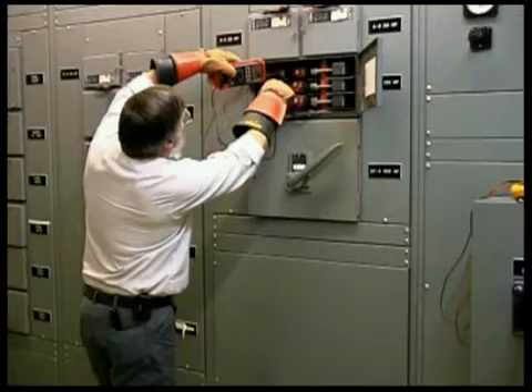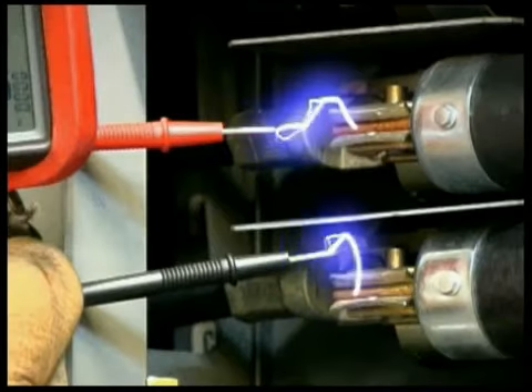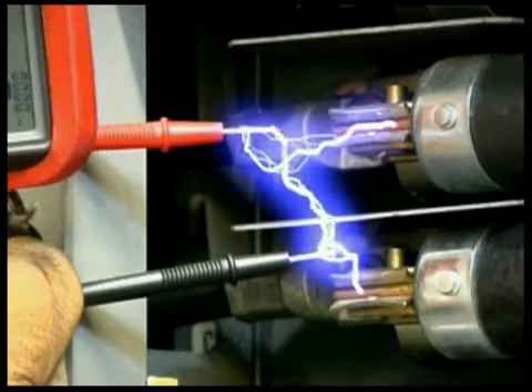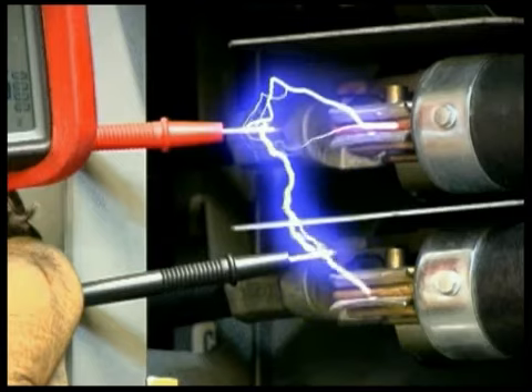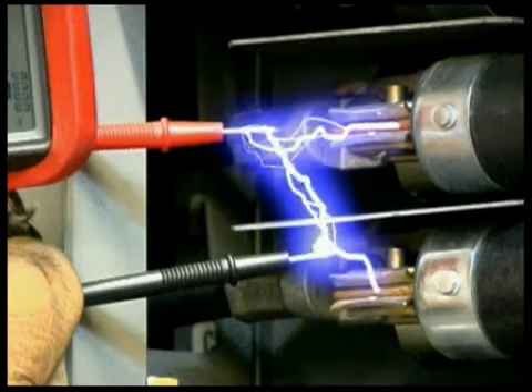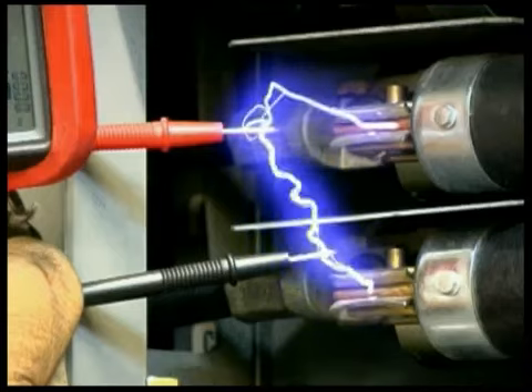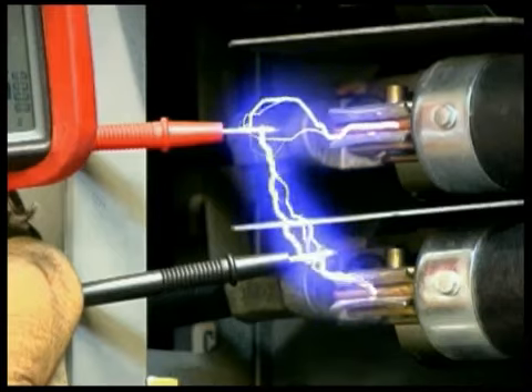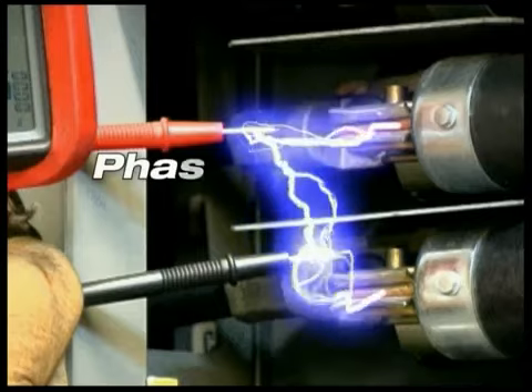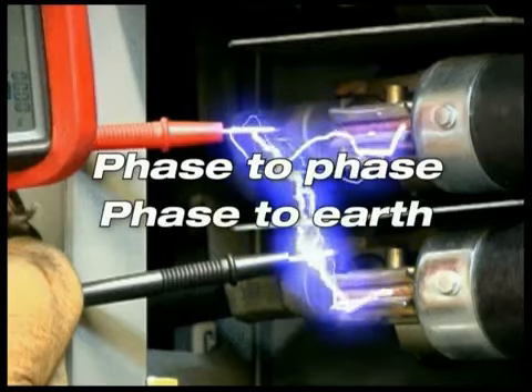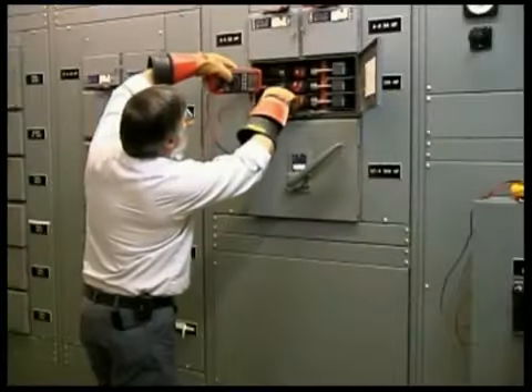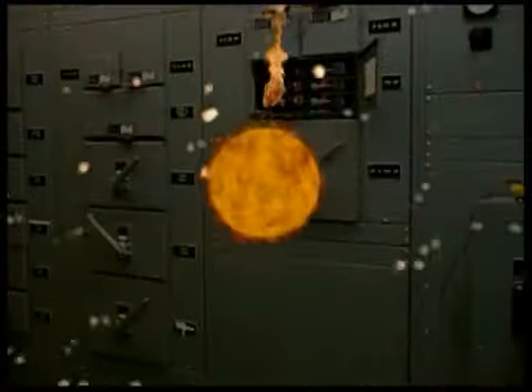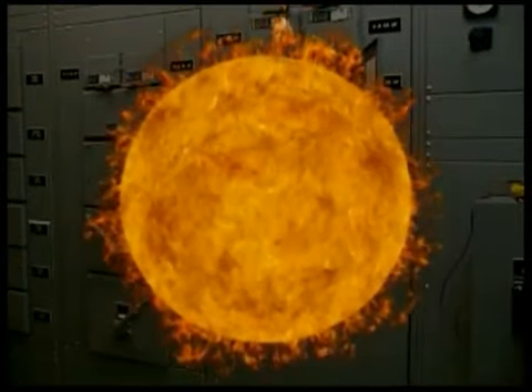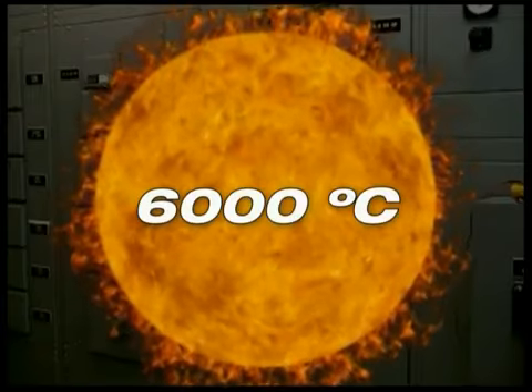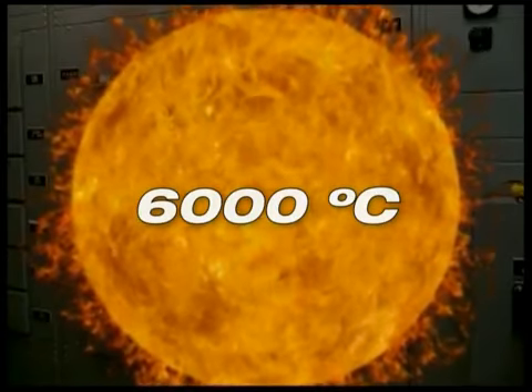The arcs follow the vaporized test probes. If these two arcs join through close proximity of the test probes, one large arc is formed, providing a low-impedance path directly from one electrical phase to another. This will cause either a phase-to-phase or phase-to-earth fault. The result is an arc blast, which can lead to a plasma fireball fueled by the energy in the system. When this occurs, temperatures can reach about 6,000 degrees Celsius.